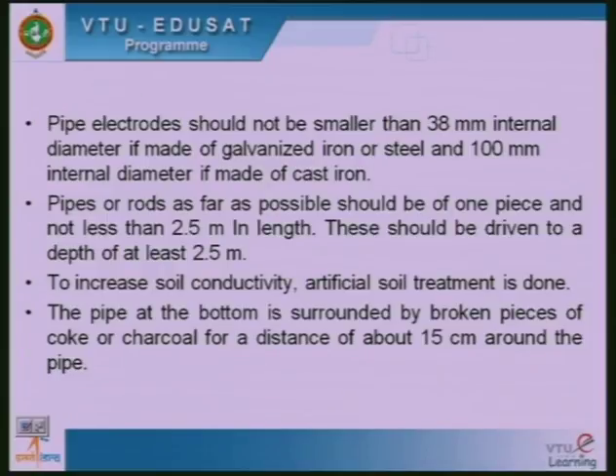Pipe electrode should not be smaller than 38 mm in internal diameter if it is made up of galvanized iron or steel, and 100 mm internal diameter if it is made up of cast iron. Okay. Pipes or rods as far as possible should be one piece and not less than 2.5 meter in length, and should not have any joints in that pipe. These should be driven to a depth of at least 2.5 meters.